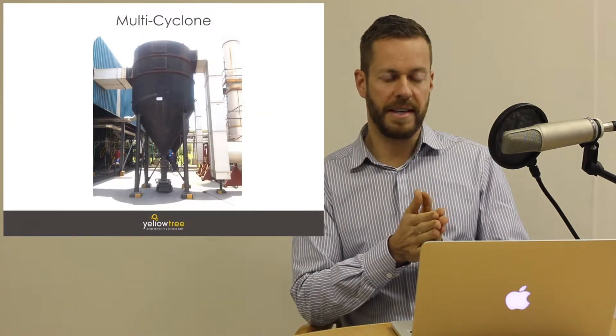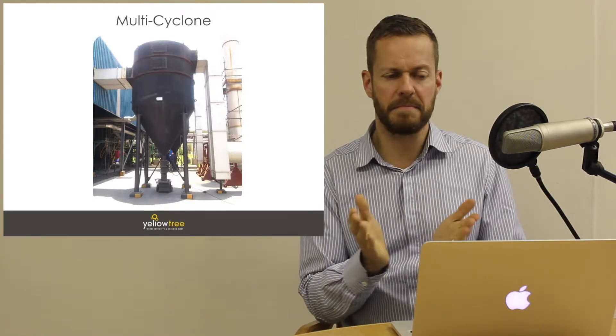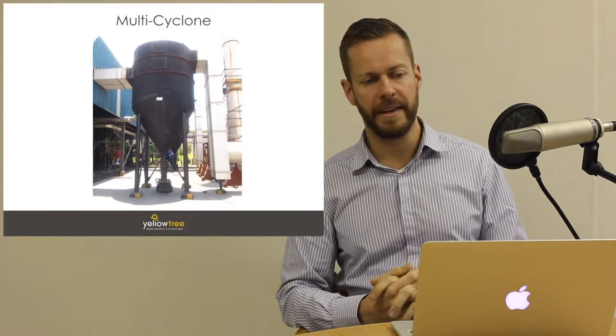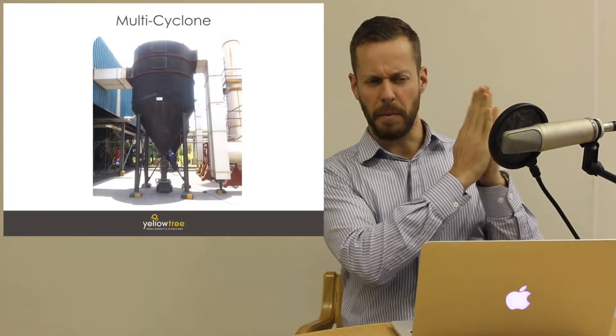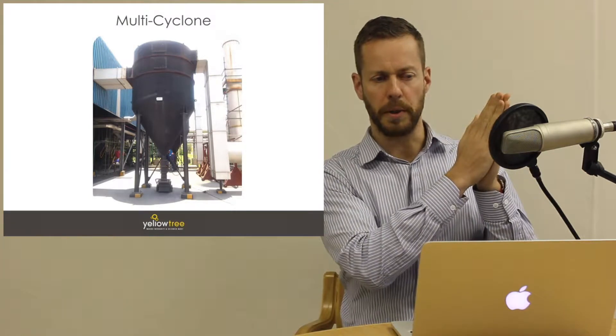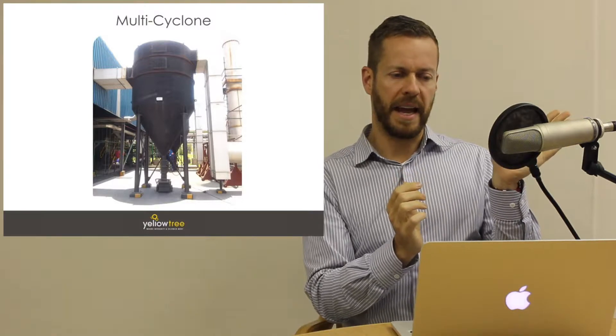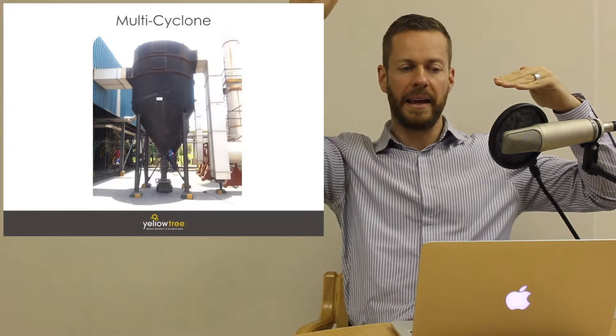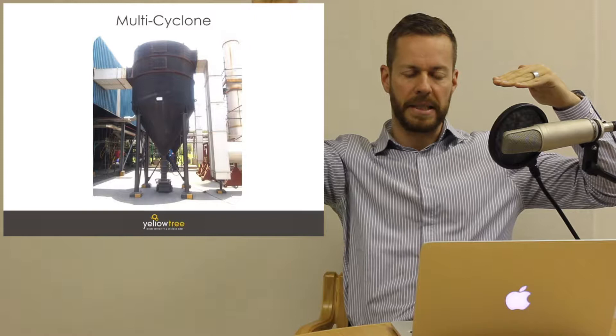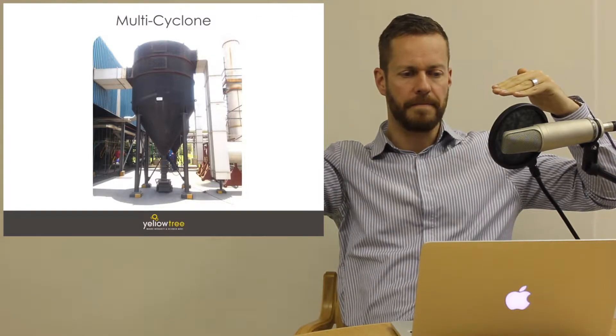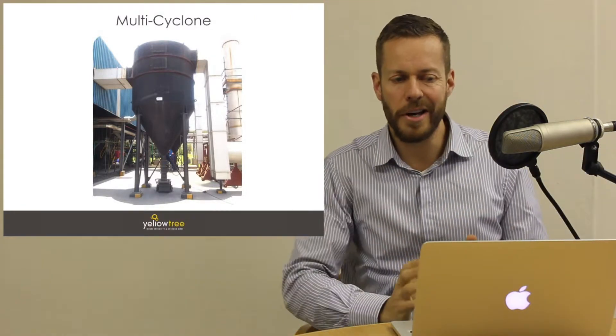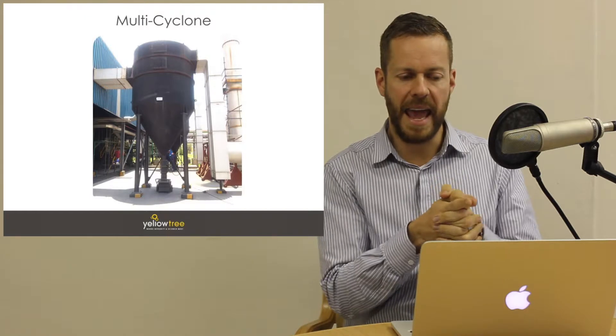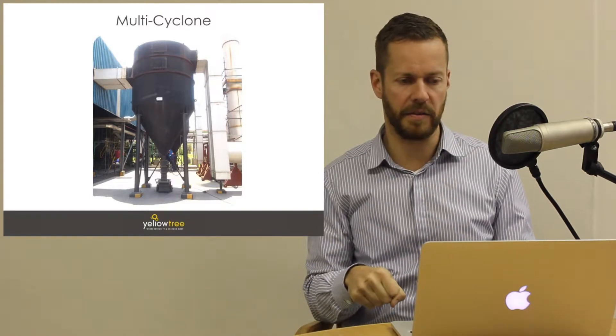That photograph shows a multicyclone, and inside there will probably be about 25 individual cyclones. Note that the air enters from the boiler house — shown in blue on the left-hand side — and enters midway in the body of the multicyclone. The clean air exits from the clean air plenum at the top, and the particulate matter exits at the bottom into a trolley — you can see the handles of the trolley — through two flaps.